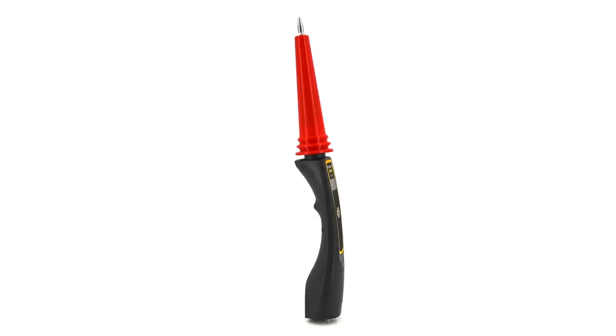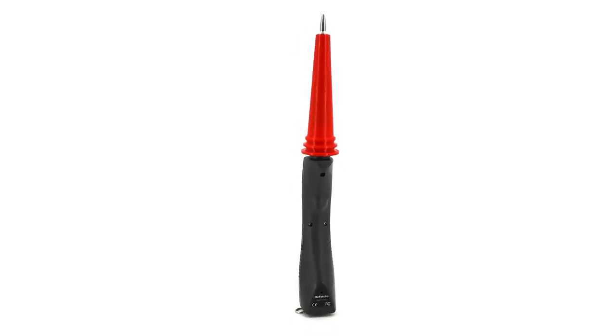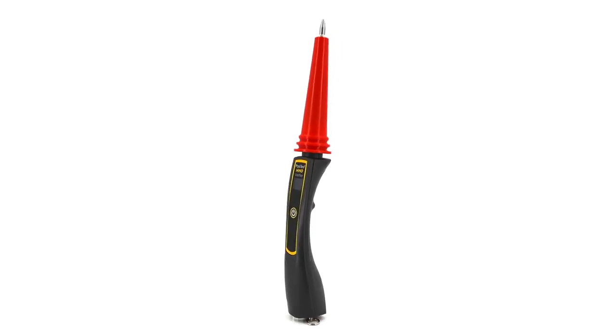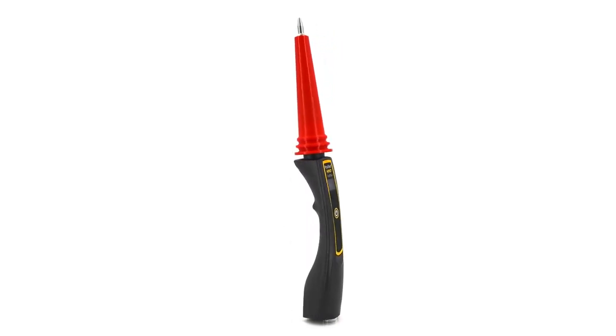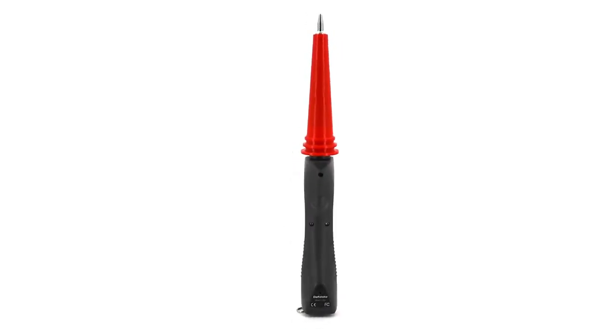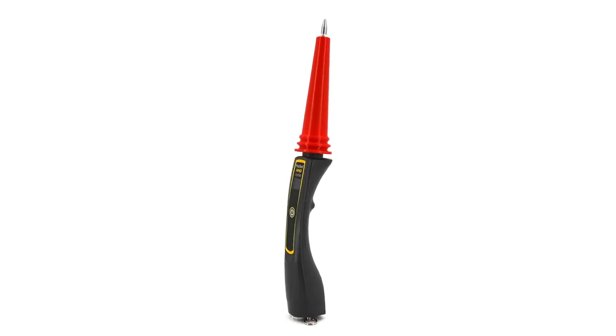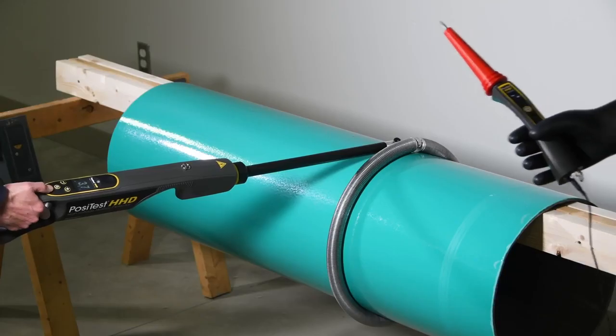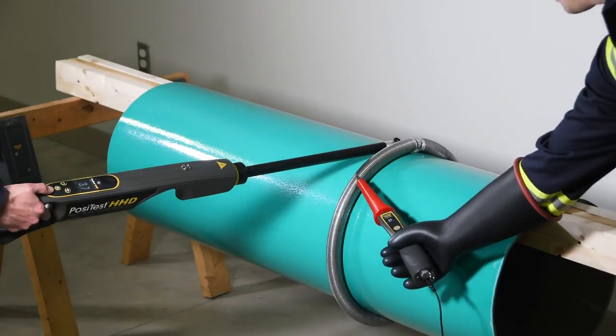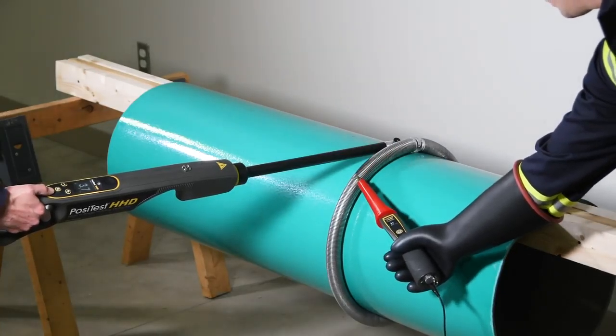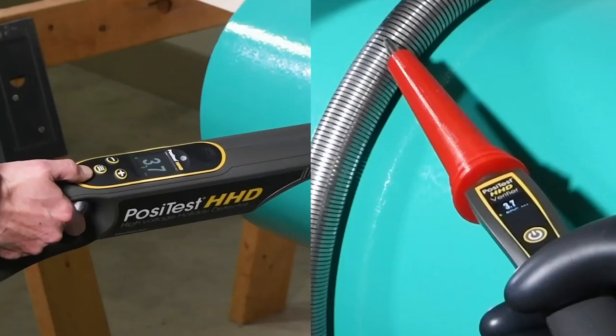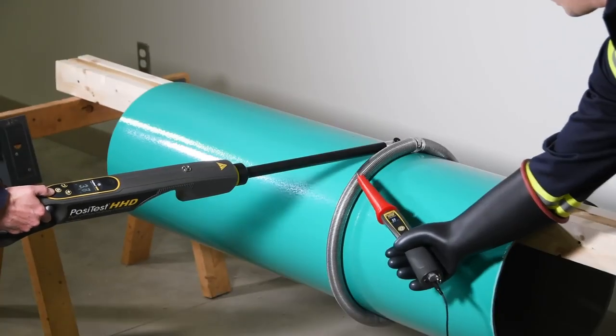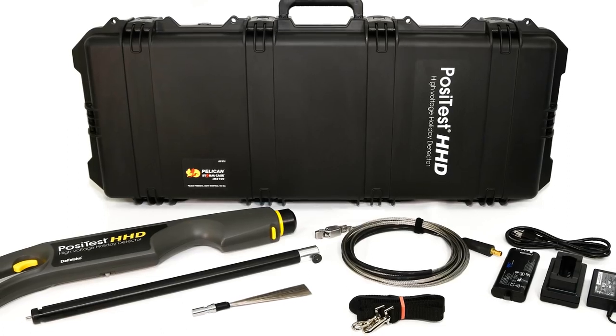For in-field verification, the Positest HHD verifier is available to verify the accuracy of any DC or pulse DC holiday detector, including the Positest HHD. Simply touch the Positest HHD verifier to the electrode while it's in use, and ensure that the voltage displayed on the verifier matches the voltage displayed on the holiday detector. It's that simple. Ordering is easy.